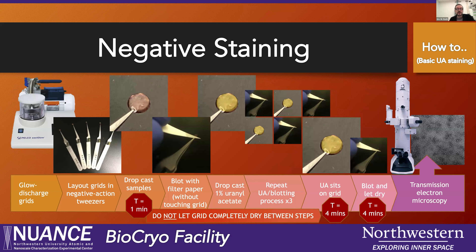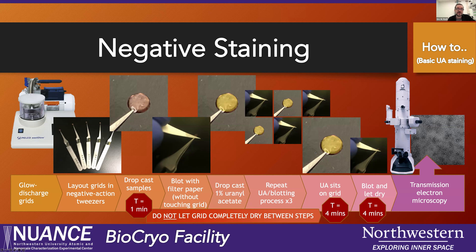So how do you negative stain? It's a very straightforward routine procedure that can be done in about 30 minutes. You begin by glow discharging. It's nice to have an array of tweezers — four or five can make things a lot easier. You start by drop casting your sample onto the grid, then blot it off and do a series of stains — for example, with 1% uranyl acetate. You don't want to let the grid dry between droplets; use filter paper to draw the liquid away slowly, trying not to touch the grid, and as soon as it's almost dry, add more. Letting it dry between steps can result in more collapsing artifacts. This can be done in about 30 minutes, and once your grids are dry, you can get them into the microscope.